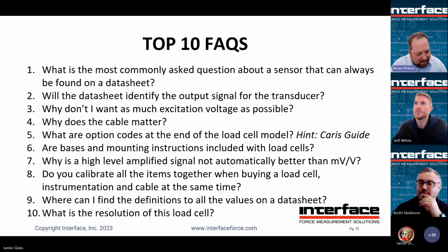Interface offers 6-wire cables. So even if your instrumentation doesn't support sense, we will at least loop it back through. Even if the sensor doesn't support sense at the bridge level, we'll still loop it through the connector. In that way, if your instrumentation supports it, you'll still be able to take that into account. Also keep in mind, if you buy a standard load cell and you're going to hook it up to a 100-foot cable run, please let us calibrate it with the cable attached. We'll be able to make sure that the cal data is representative of what you'll actually see.